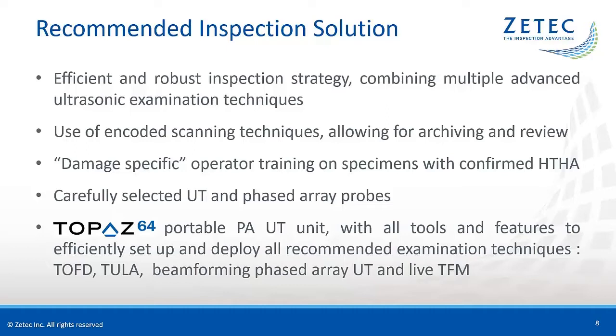The use of carefully selected UT and phased array probes is important in order to optimize the performance of the applied examination techniques. And finally, efficient deployment of this inspection strategy requires a powerful portable phased array unit like ZETEC's Topaz 64, with all the tools and features to set up and execute the recommended examination techniques that we will discuss in the upcoming slides: TOFD, TULA, beamforming phased array, and live TFM.